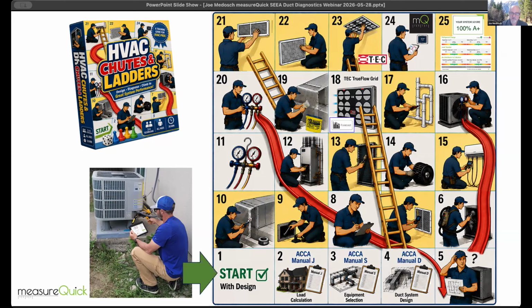So now my forecasting method is going to tell me whether or not these ducts are sized correctly for my system that's there, or maybe they just need a few tweaks or adjustments to try and get the airflow out to certain areas. So I'm sealing it up or determining what I need to do to adjust those ducts, and then I jump up and make sure that my registers and my filter, and I have to use the TrueFlow grid again after I put in a new system to commission it with the airflow, and then confirm it with MeasureQuick to confirm that I actually have the correct refrigerant charge and the correct airflow. And now I'm able to get a score out of that final.